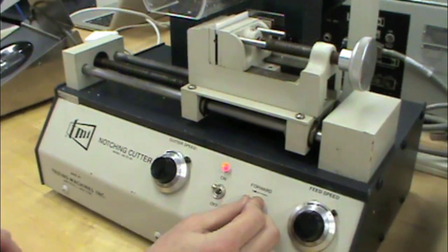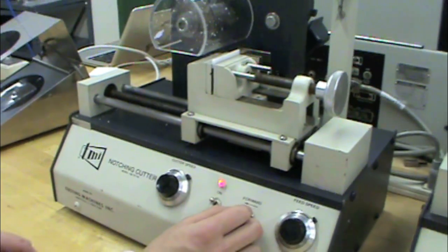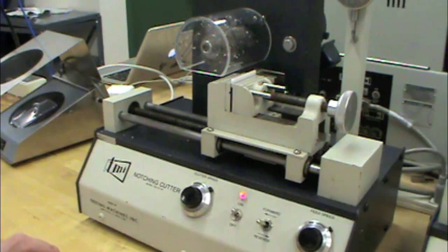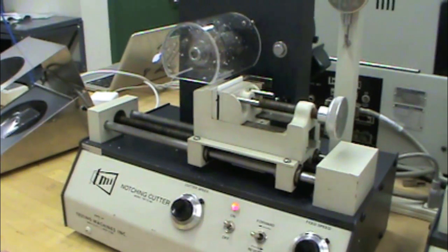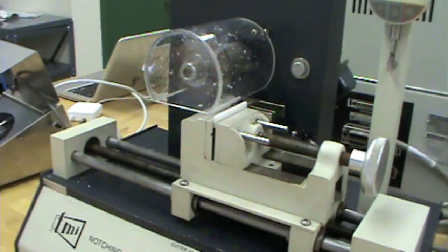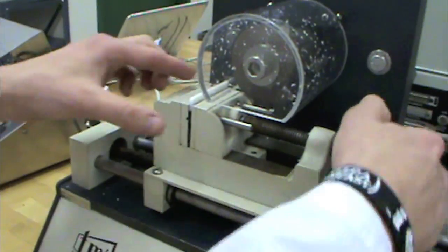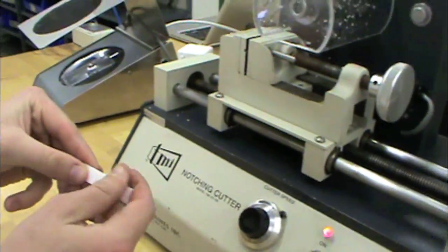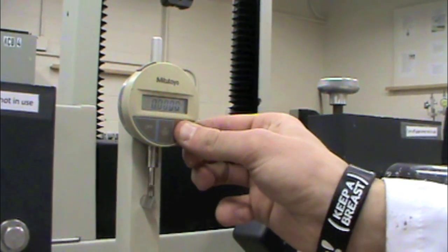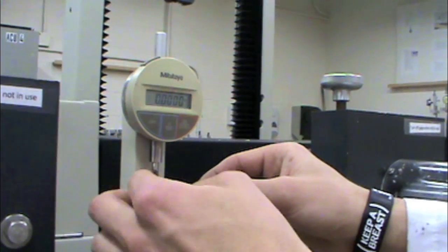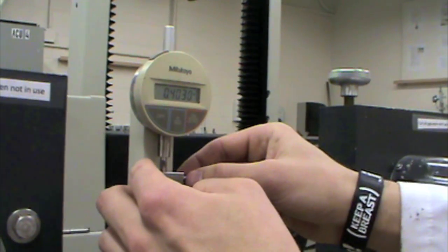Be sure to use the guide so that the blade will cut the test specimen in the center. Turn on the cutter and then set the vise in motion towards the cutting blade by flipping the toggle. Set the vise and unload the test sample after the part has cleared the guard. Set the vise back into the starting position after this is done. Next, take the steel block from the machine and place it into the Mitutoyo measuring gauge and zero it out. This steel block measures 0.4 inches.